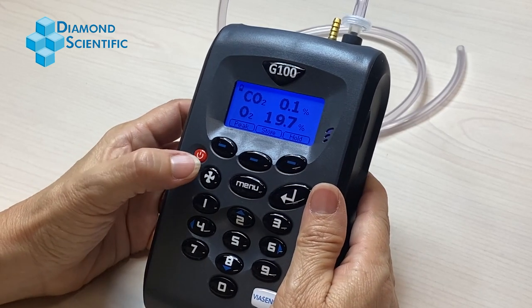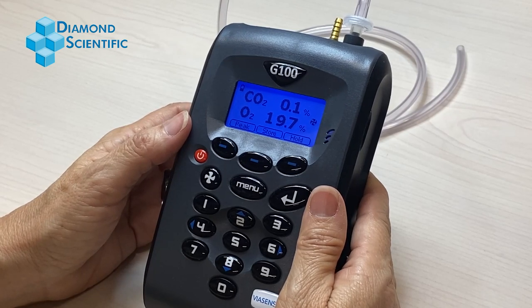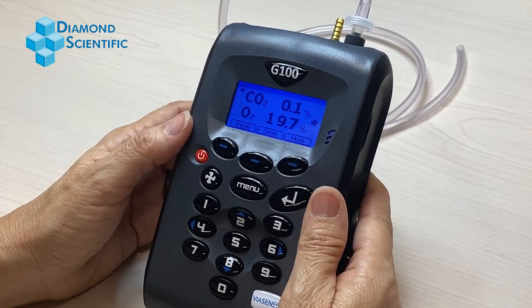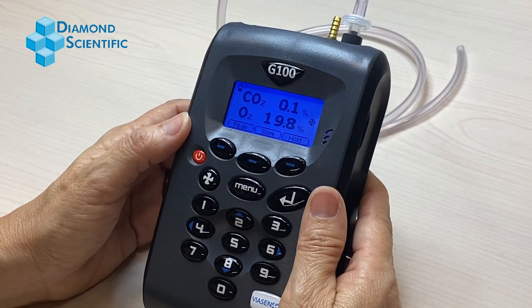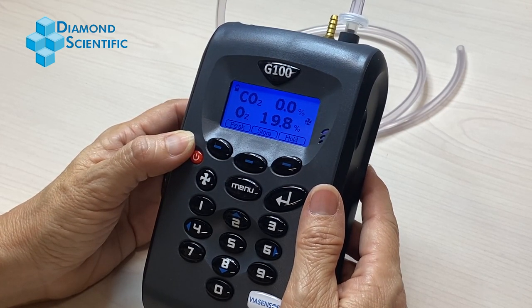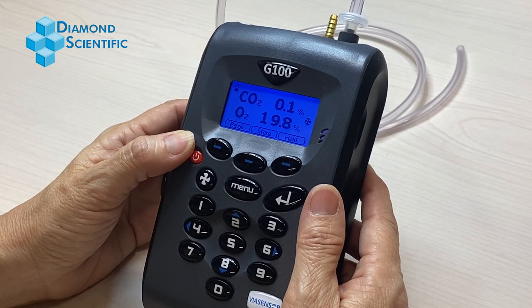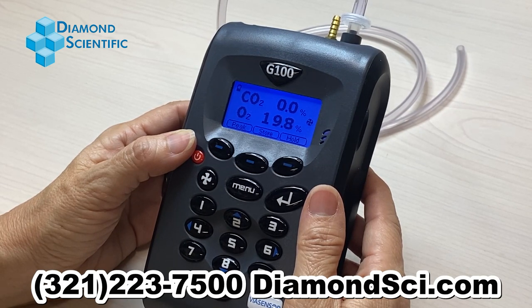Exit the menu and turn your fan on. If it still fails, repeat these steps for fine tuning. If you reach positive 16 and the unit still messages a flow failure, the unit should be submitted for factory servicing. If your instrument needs calibration or servicing, contact Diamond Scientific at 321-223-7500 or reach us through our website at DiamondSci.com. Thank you.